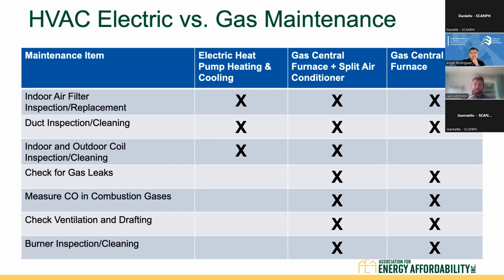Where we get to more specifics on heat pumps is indoor and outdoor coil inspection / cleaning. That's going to be required for your heat pump. That's also going to be required for your split air conditioner. Heat pumps are air conditioners. They can just go in reverse. So the maintenance is the exact same between a heat pump and a split air conditioner, or a packaged heat pump and a packaged window AC. The maintenance is going to be the same for those.